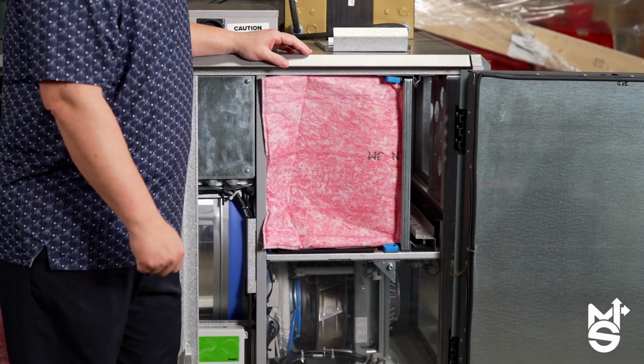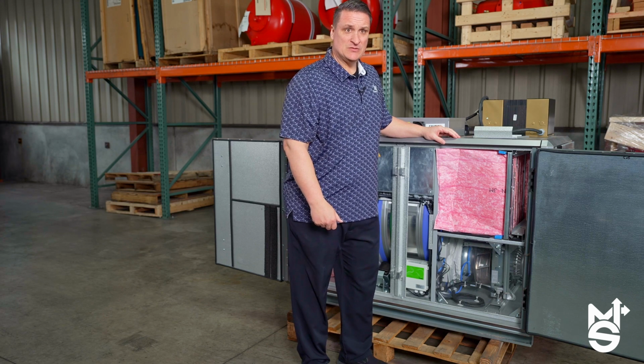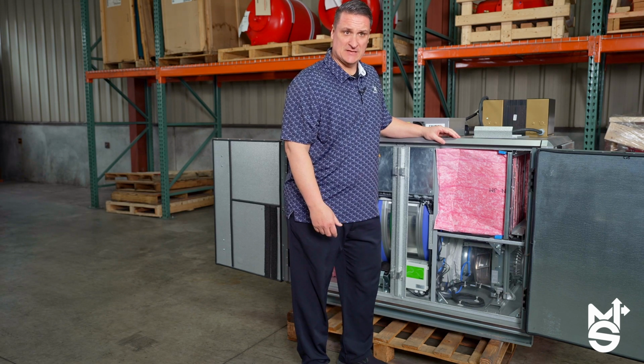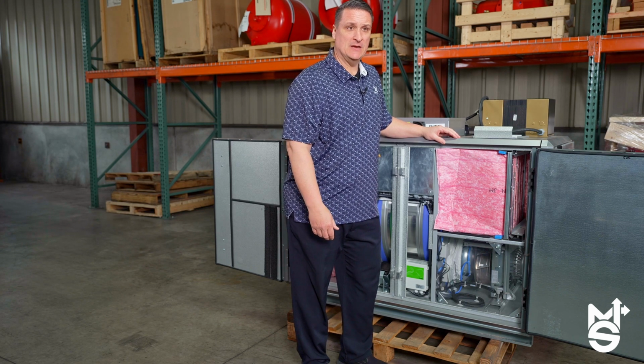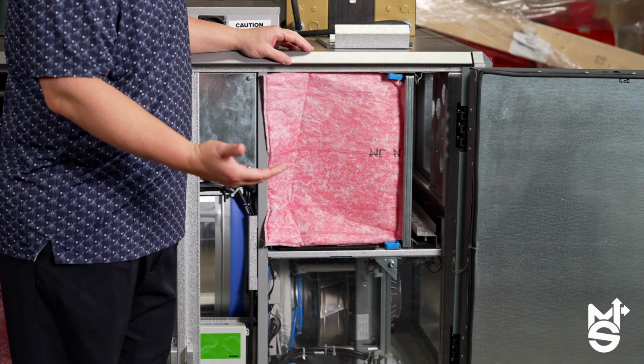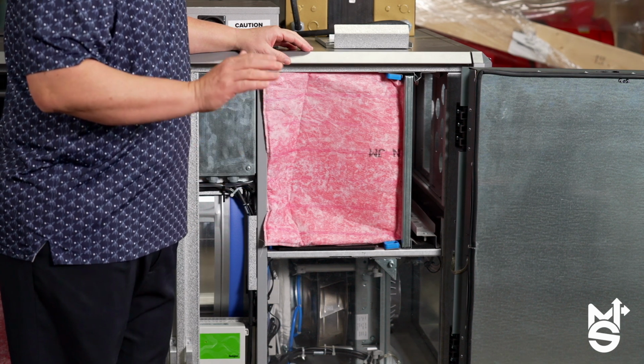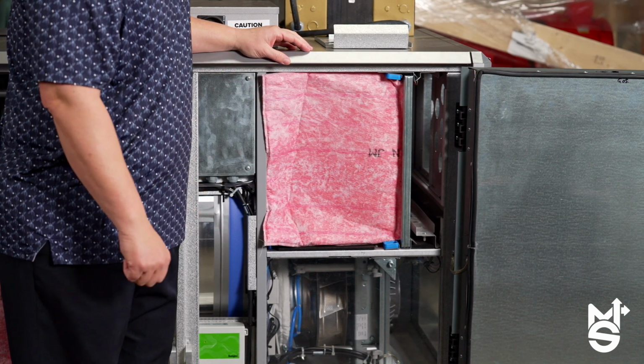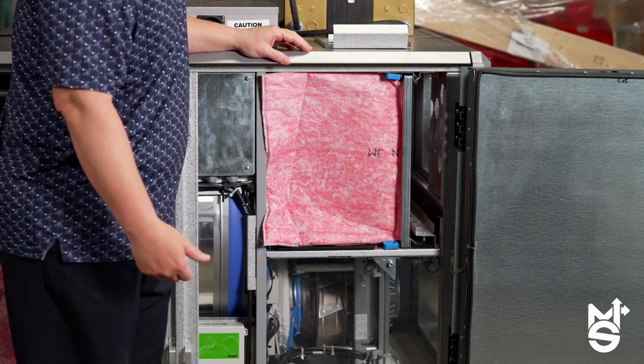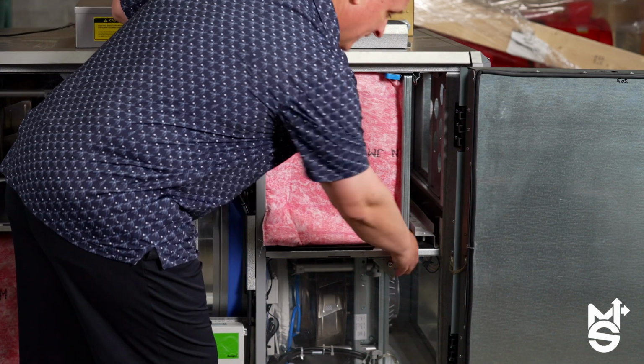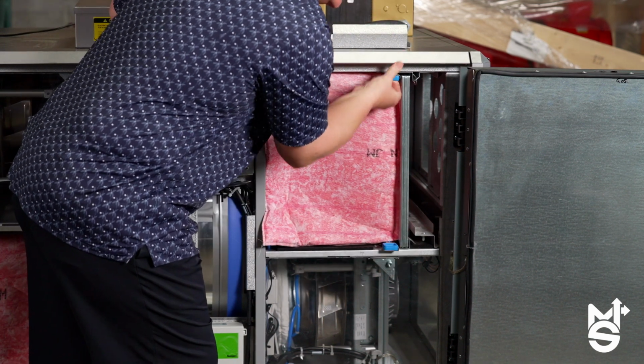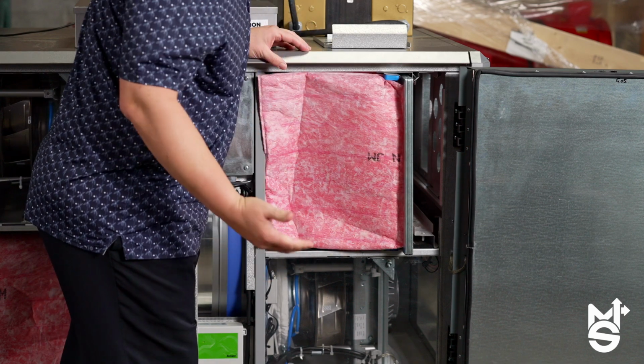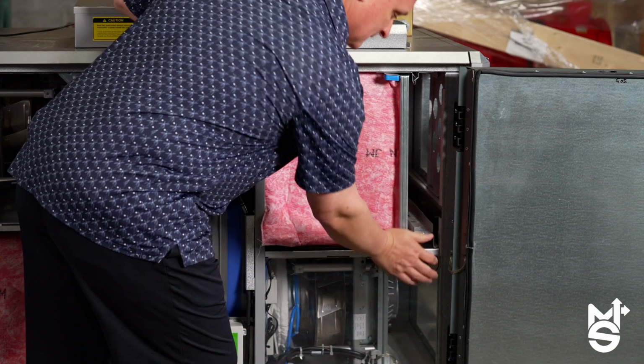Swegon filter racks are designed for mechanical sealing to properly prevent air and particulate from bypassing the filter media. The rack includes a mechanical lever to seal the filters and reduce leakage to a fractional percentage of the nominal flow rate. I have to mechanically disconnect this filter from the ERV in order to service it.